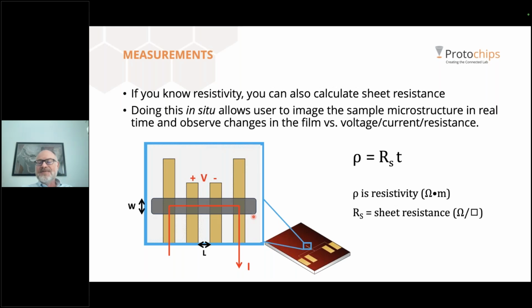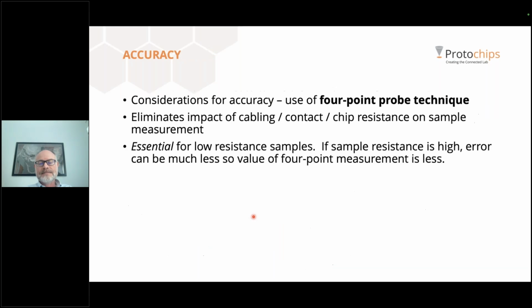So things like this help the industry move in the right direction in terms of its process technology. Now let's talk about accuracy. I mentioned the first part, which is the use of a 4-point probe technique. This technique eliminates the impact of cabling, et cetera, and it allows you to get the most accurate results, especially for conductive samples. But there are other considerations that are equally or sometimes more important and that are impactful for all types of samples and all types of measurements.